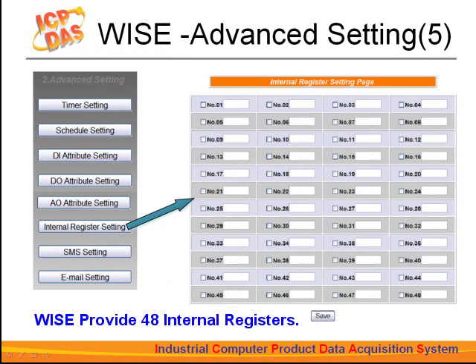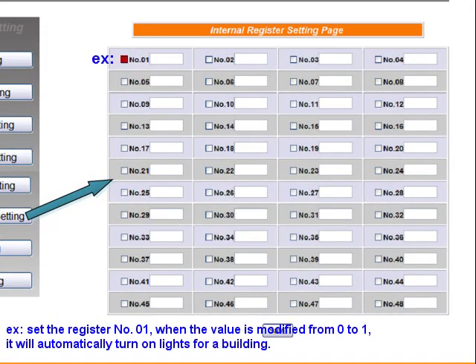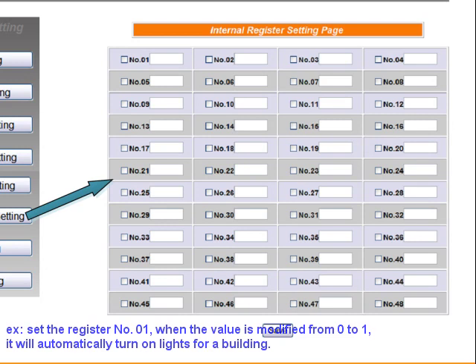WISE provides 48 internal registers. They can be used to hold temporary variables for your edit rules without occupying real channels. These registers can be modified via Modbus TCP. For example, you can write to internal register 01. When its value is modified from 0 to 1, it will automatically turn on lights in a building. You can set a button from the control center, so when you click on the button, the value of internal register 01 will be changed to 1 to trigger the criteria of the rule related to lighting control.